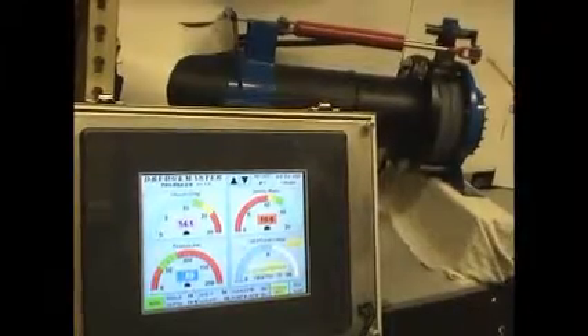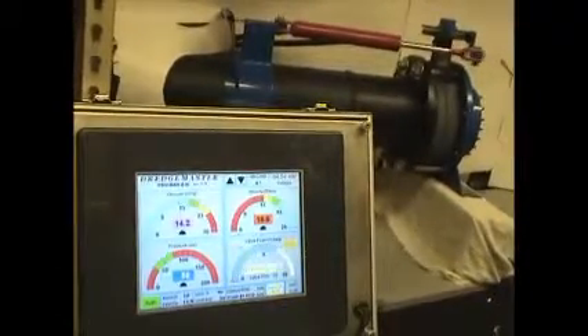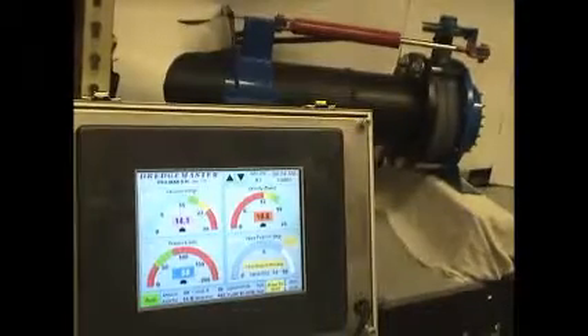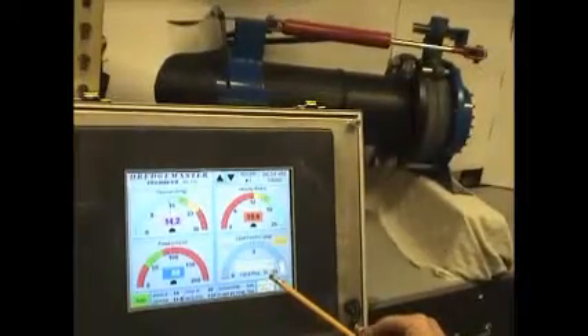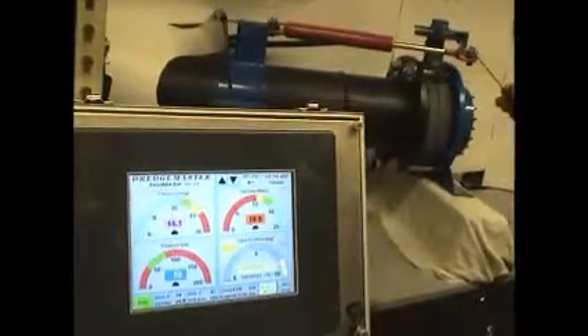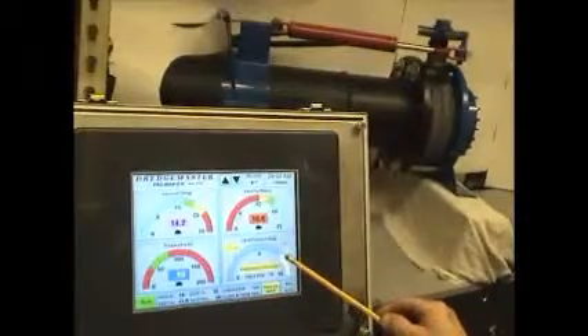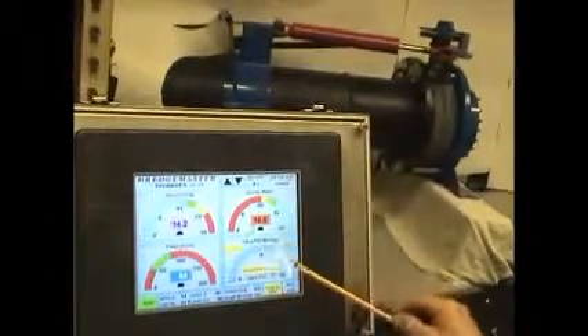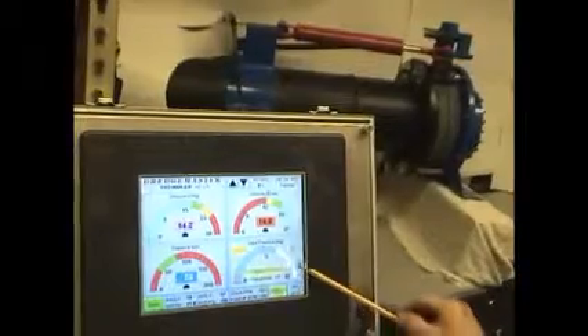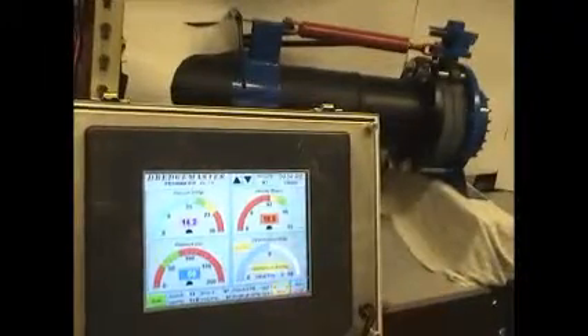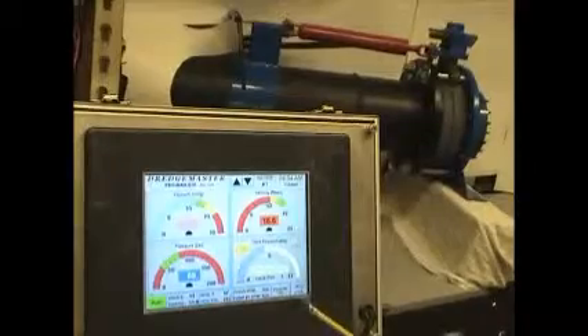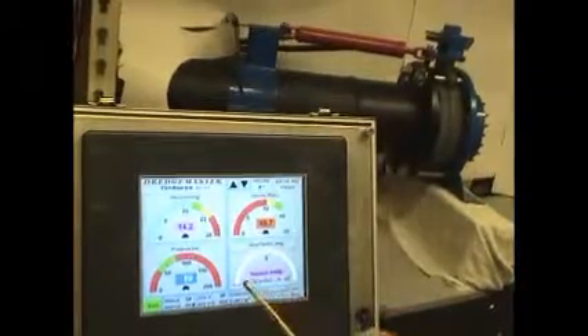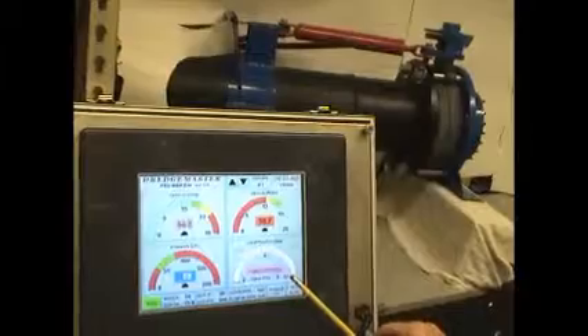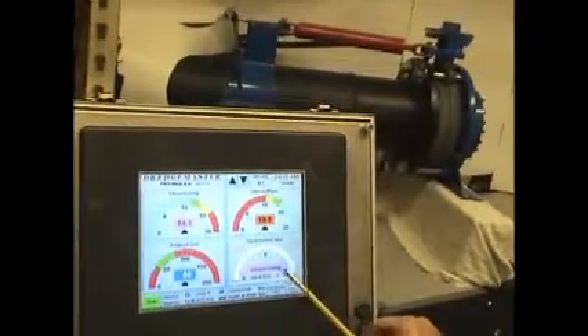Once the cylinder has fully extended itself all the way, it will automatically reverse directions. You can see our valve position counting up. The cylinder has now reversed itself. You can see it's starting to close down. It counted how many of these segments it took to open. Now it's counting how many of these segments it's taking to close. Okay, it just closed up. So what happened here is it calibrated and says it took 17 segments, the 17 here, to fully open.